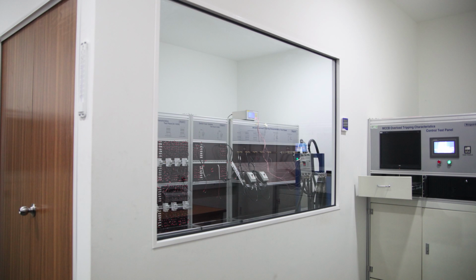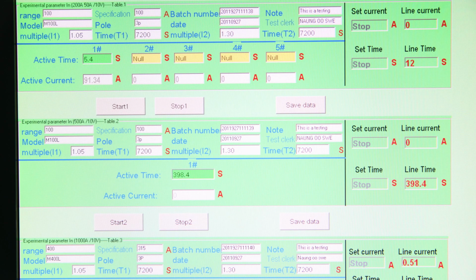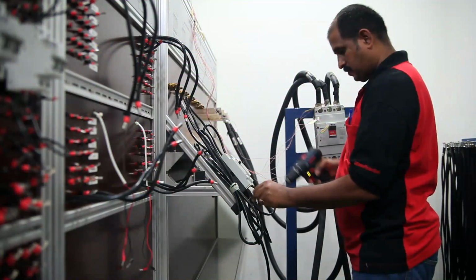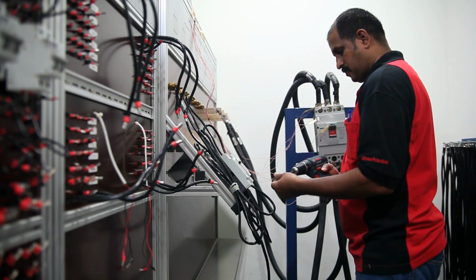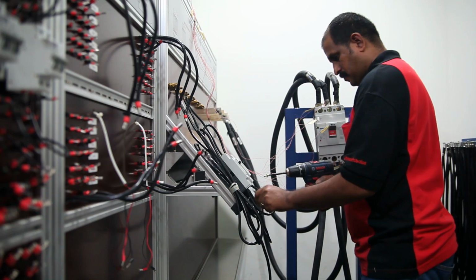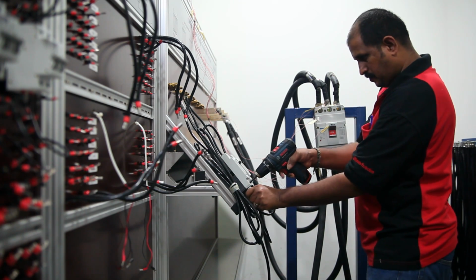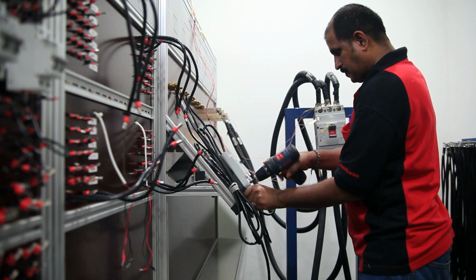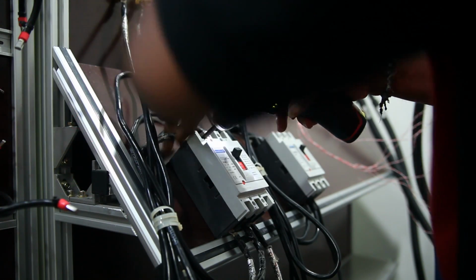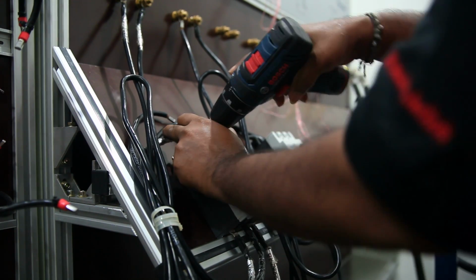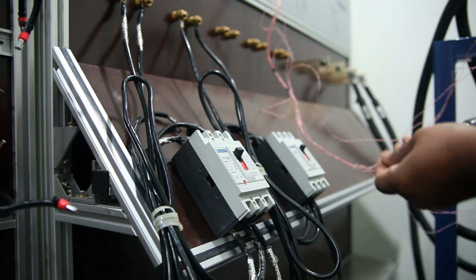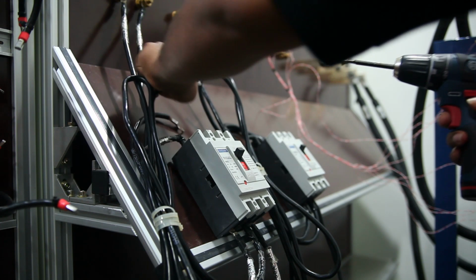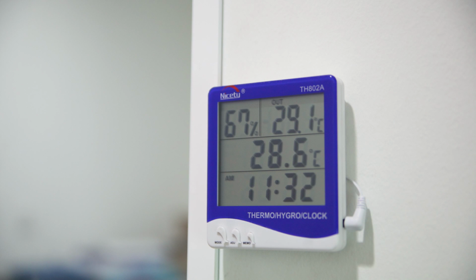Overload current tripping test thermal for MCCBs. A conventional non-tripping current of 1.05 times is injected into the MCCB in a cold state, and no tripping should occur within a conventional tripping time. Immediately, the current is ramped up to 1.30 times for tripping to occur within the conventional tripping time. Testing is performed pole by pole, and all poles are energized together.